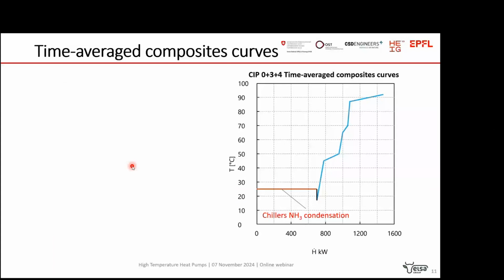From these measurements, we can draw the composite curve. Here we consider only the condensation of the ammonia chillers as a heat source, and as a heat sink we have the heating of the makeup water. We also have the recycled tank heating, so that we increase the temperature of the tank and reduce the heat supplied by the inline heat exchanger. The same goes for the acid tank, which is quite small, as I mentioned, and for the soda tank we have quite a large heat demand. So this is the basis, or the start, for integrating the heat pump.